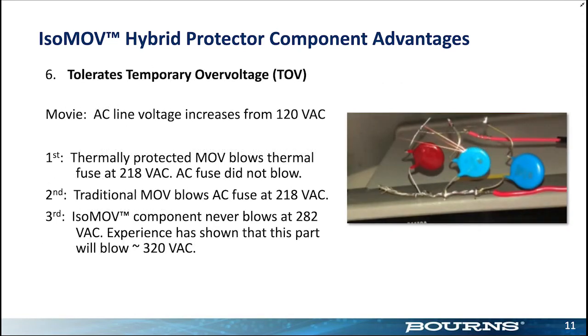Temporary overvoltage is a common hazard for AC lines, right? You've got a compressor turning on or off, or some motor, and the voltage swells up to a higher voltage than normal for a short time. It could be hundreds of milliseconds or even longer, long enough to cause some problems. So how does this stack up against temporary overvoltage?